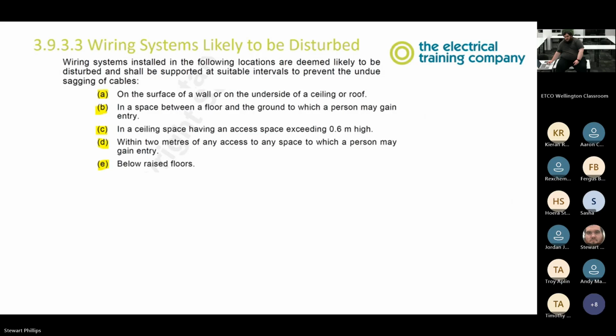So, wiring systems likely to be disturbed. Installed in the following locations are deemed likely to be disturbed and shall be supported at suitable intervals to prevent undue sagging of these cables. So, on the surface of a wall or on the underside of a ceiling or roof, in a space between a floor and the ground to which a person may be given entry. In a ceiling space having an access space exceeding 0.6 meters high. Within 2 meters of any access to any space to which a person may gain entry, and below raised floors.